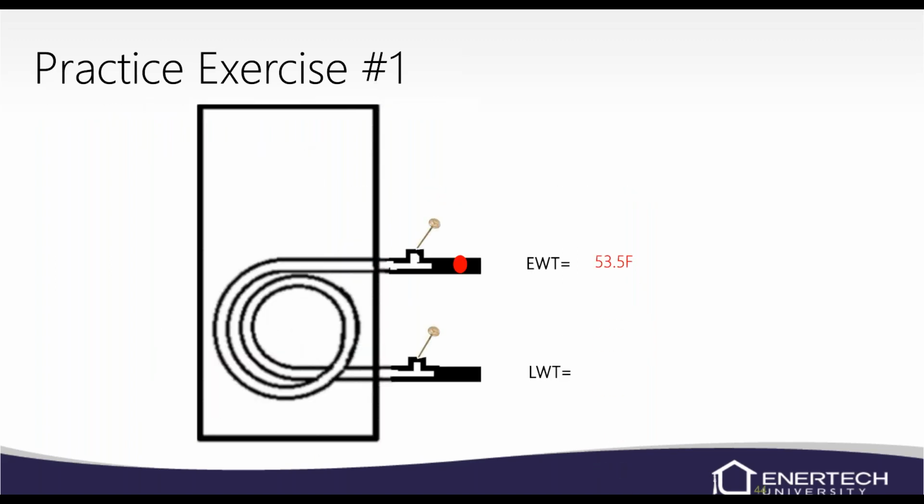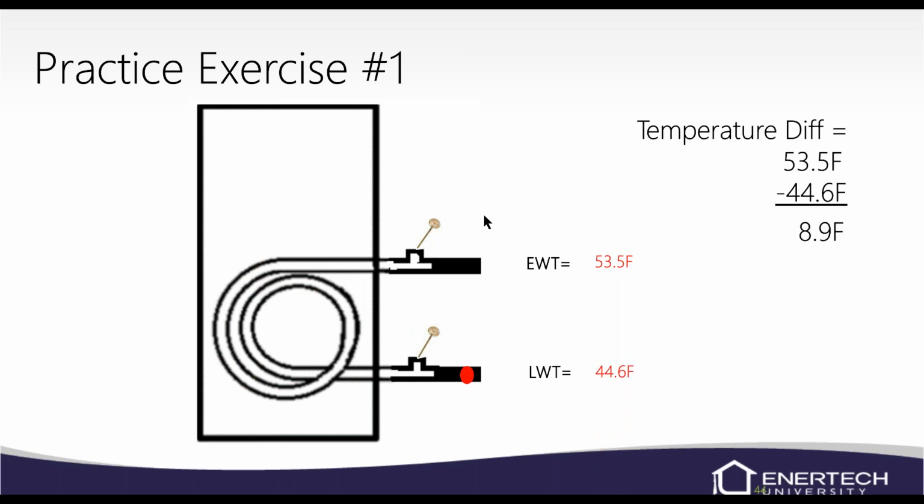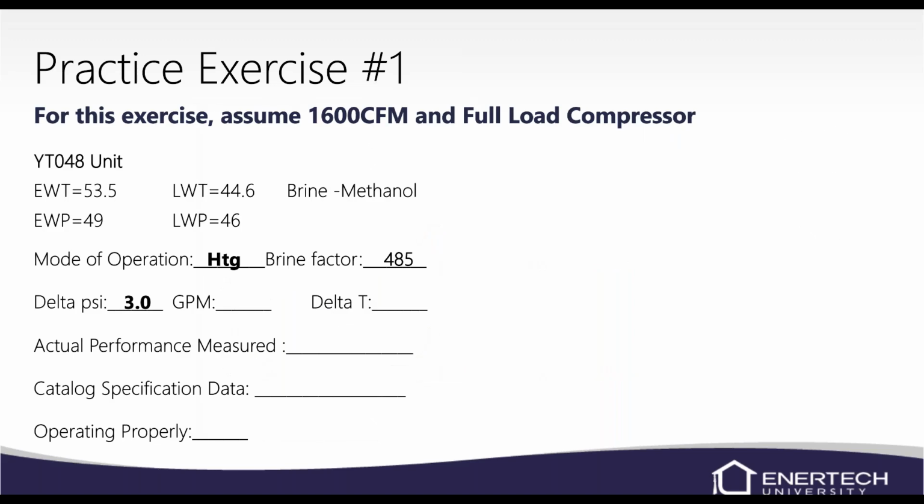Next, we'll look at our entering water temperature of 53.5 and we're leaving at 44.6. So if we look at this, our entering water is higher than our leaving water, so we're in heating mode. Do the math on that, and we got an 8.9 degree temperature difference. So I told you again, since we have a higher entering than leaving, we're in heating mode.